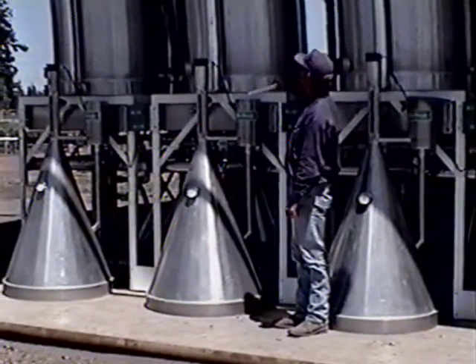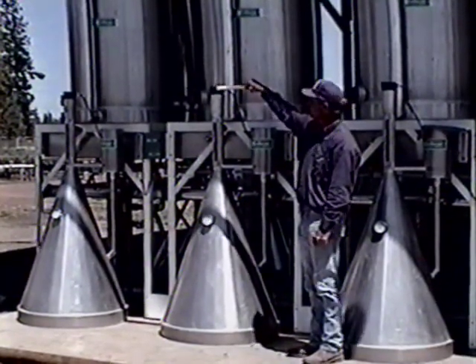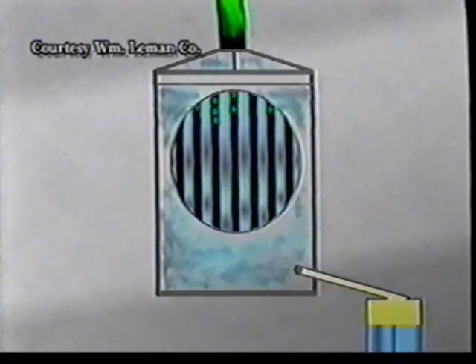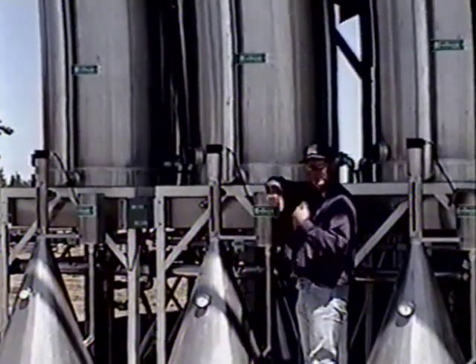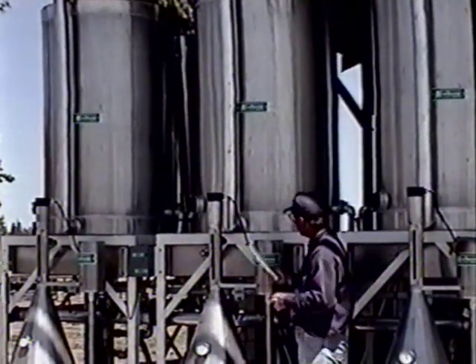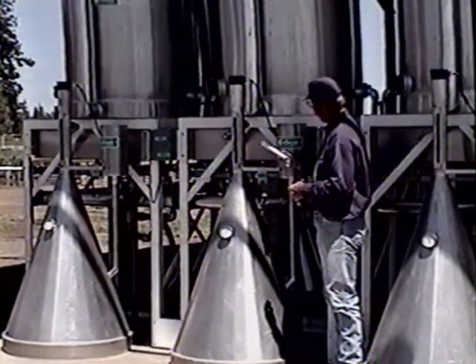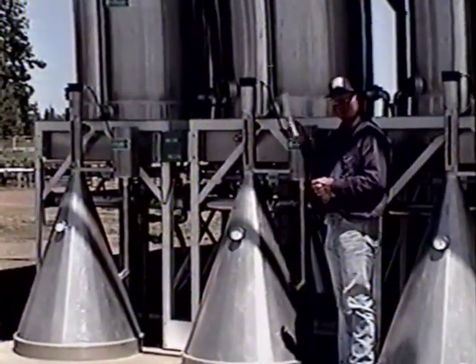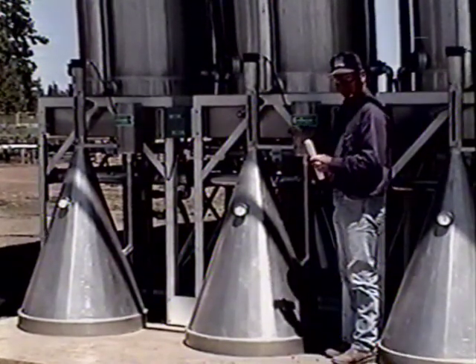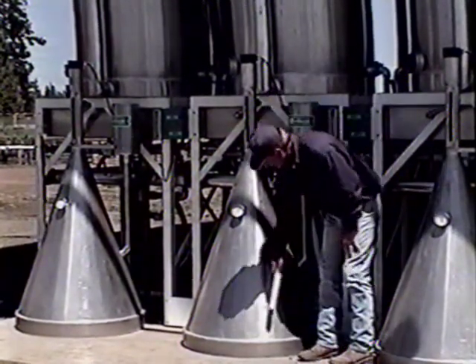This is the condensing separating mechanism we use in the mint distillery. The oil and steam vapor that we've created in the tub and captured, brought in through the aluminum piping system, goes into the top of this unit. This is called a condenser. The vapor comes down through those pipes, which are surrounded by water on the water side of the condenser. As the vapor moves down, we take it from 250 degrees down to approximately 120 degrees at the bottom of the condenser where the vapor exits, and it's now a liquid. This temperature is controlled by electronic valves that regulate the flow of cold water around the condensing tubes inside the condenser. So as it leaves the condenser, we've taken our mint oil and steam vapor and created a liquid solution out of it, which enters the separator can at the bottom.